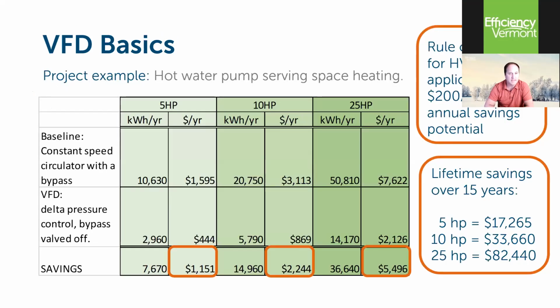So here's some basics. Rule of thumb for HVAC VFD is about $200 per horsepower annual savings potential. This is going to vary, of course, but if you're out in the field or you're in your boiler room or your facility and you're looking at motors on pumps and fans, and you're wondering, is this motor or this fan or pump worth controlling? $200 a horsepower is a starting point. We can refine that through analysis. We have a lot of tools at our disposal here at Efficiency Vermont. We do a lot of power logging on larger motors, typically at least 5 horse and above. The smaller horsepower stuff, we usually just estimate on paper.